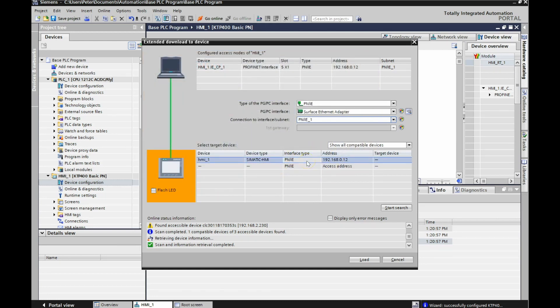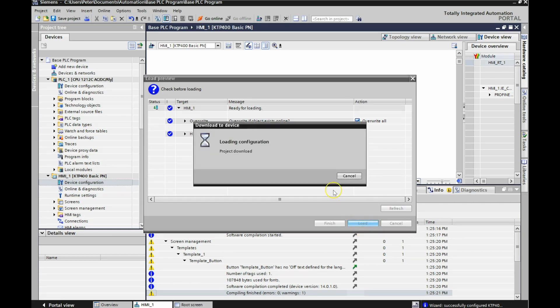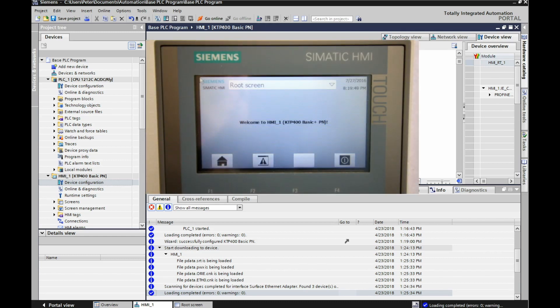Select that HMI at 192.168.0.12 and click load. When you see the next window — 'overwrite if object exists online' — select 'overwrite all' and then hit load once more. We've set everything up. We now should have communication between our PLC and our HMI. You should now see the root screen on your HMI. We haven't put any push buttons on there yet, but we've set up communication between our PC, our PLC, and our HMI.